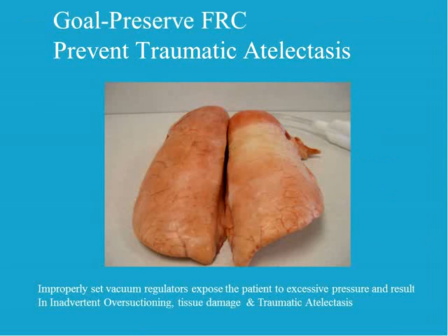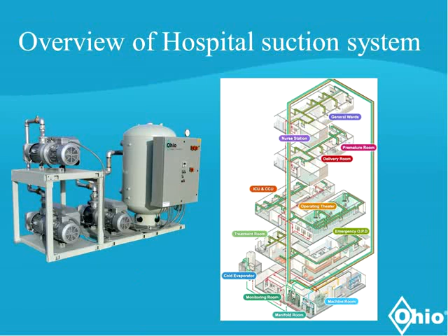So, a patient in the intensive care unit might be using 4 or 5 vacuum regulators, depending on how many chest tubes they have, if they're doing subglottic secretion removal, endotracheal tube suction, nasogastric suction, etc. And then you have your operating room suite, which is the only area of the hospital where it's okay to use wide open suctioning continuously, and that's because they're irrigating surgical fields. So you've got to have enough power to supply vacuum through the entire campus.